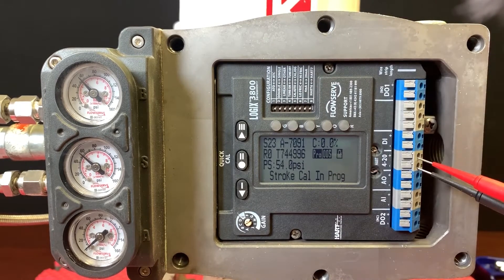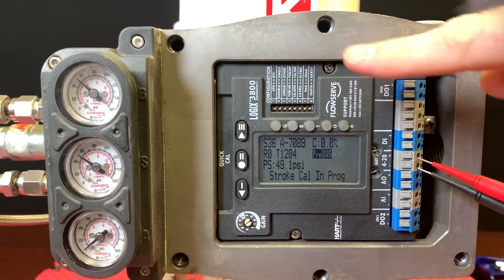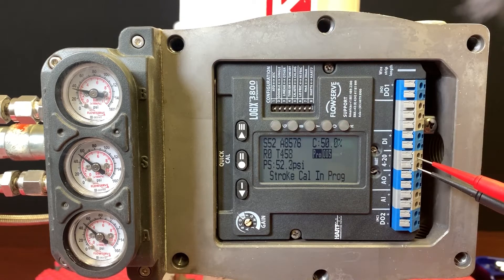You're going to see a state change — it's going to say 'stroke cal in progress,' then it's going to go through scoping the valve and finding the limits. Should the valve have stops, if it doesn't, you may have to do what's called a cal jog where you actually set them manually. This process just takes a few seconds, and depending on the size of the valve and the volume being moved, it may take a little longer.